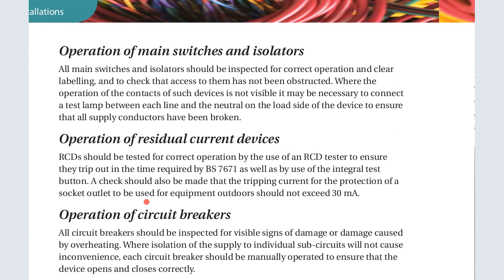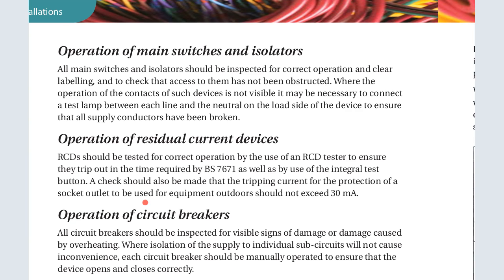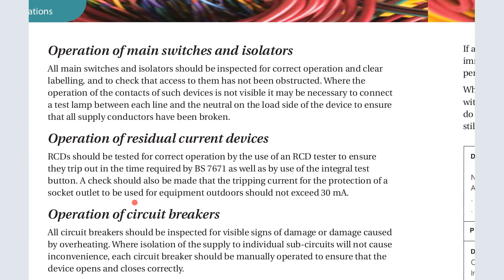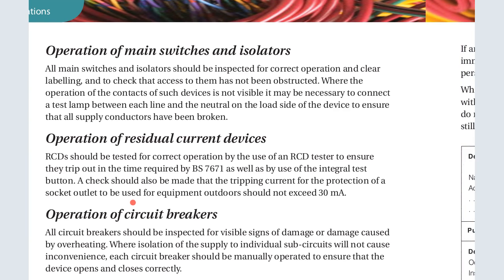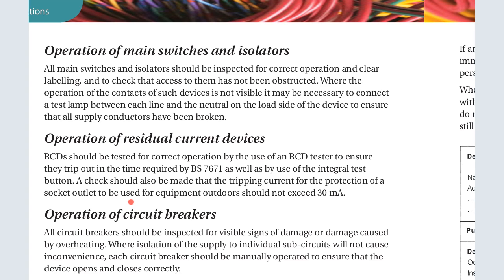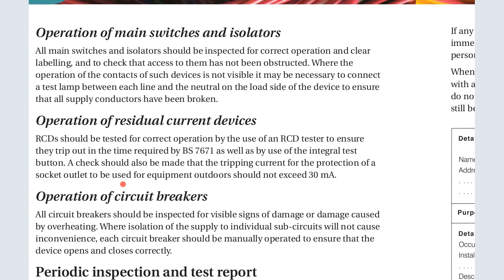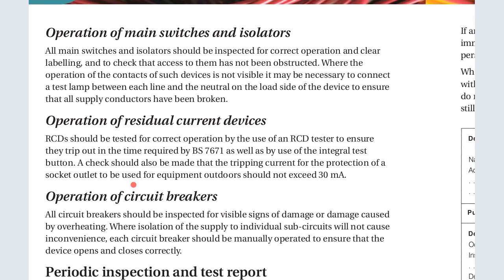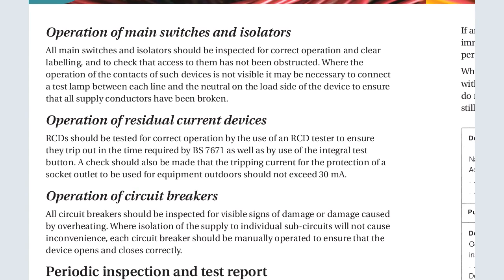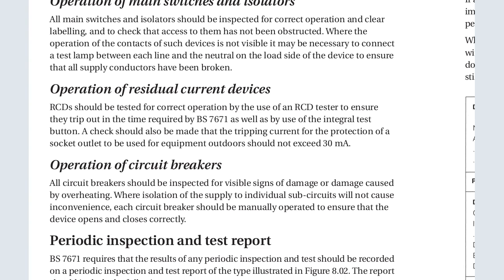Now, the operation of the main switch and isolators. All main switches and isolators should be inspected for correct operation and clear labeling, and to check that access to them is not obstructed. Where the operation of the contacts of such devices is not visible, it may be necessary to connect a lamp test between each line and neutral on the load side of the device, to ensure that all the supply conductors have been broken.